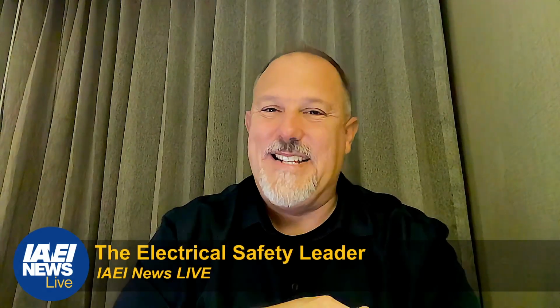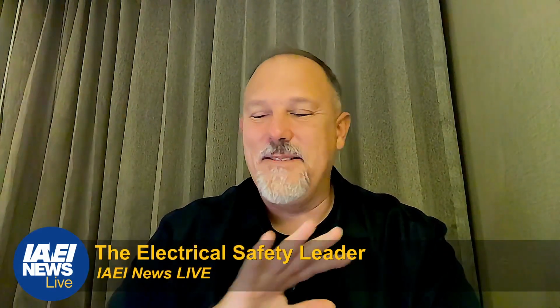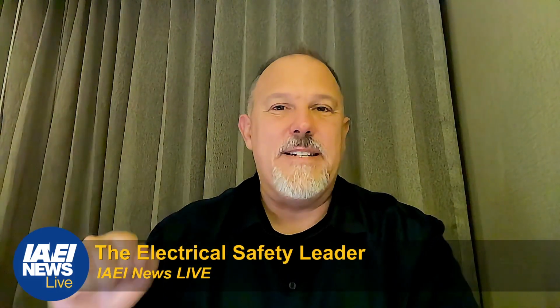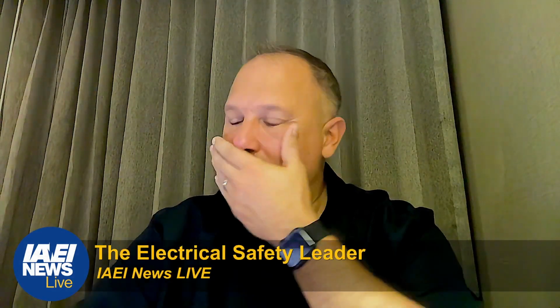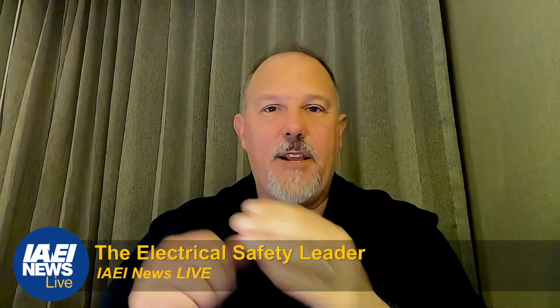If you've never seen that, it's really cool. But when we did it, it was so, I'm not even going to say how unsafe it was. But anyway, we would cut wire and demonstrate that a thermal mag breaker would not trip and an AFCI would trip, and explain the technology. And after break, we would go into the meeting room and sit and watch the educational program.